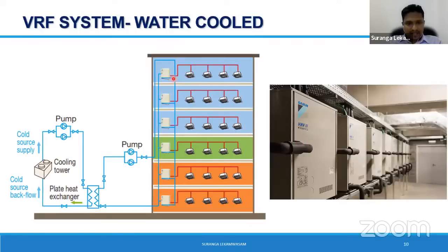In this particular system, on the condenser side, they have a heat exchanger, which is actually a plate heat exchanger, right? Plate heat exchangers are very vulnerable to water quality. Therefore, manufacturers demand that you have a closed condenser water circuit. You cannot run on a cooling tower system, because a cooling tower is an open circuit where water quality is only somewhat tolerable. Therefore, they ask you to go for a closed type cooling tower system, which adds a lot of cost, operational costs, design issues, etc. Therefore, I think that would be the reason why this is not commonly used in Sri Lanka.